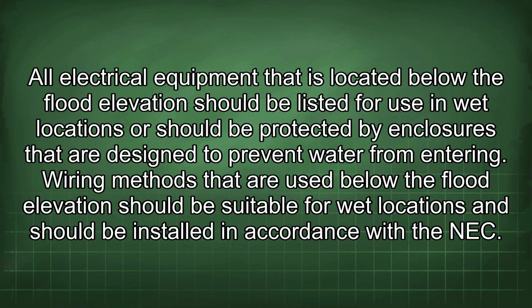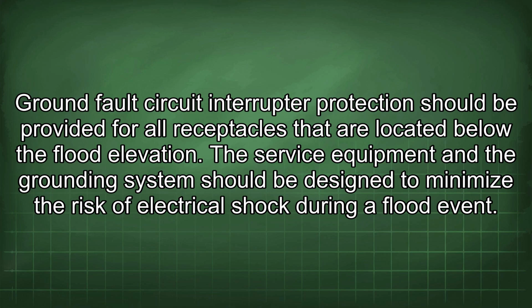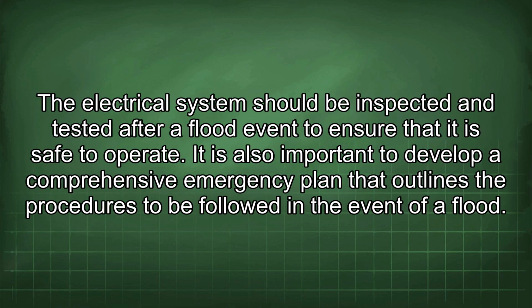Ground fault circuit interrupter protection should be provided for all receptacles located below the flood elevation. The service equipment and grounding system should be designed to minimize the risk of electrical shock during a flood event. The electrical system should be inspected and tested after a flood event to ensure that it is safe to operate. It is also important to develop a comprehensive emergency plan that outlines the procedures to be followed in the event of a flood.